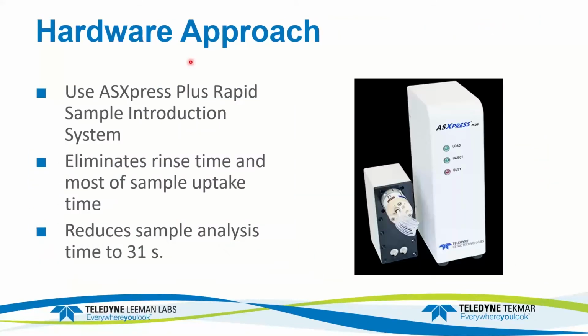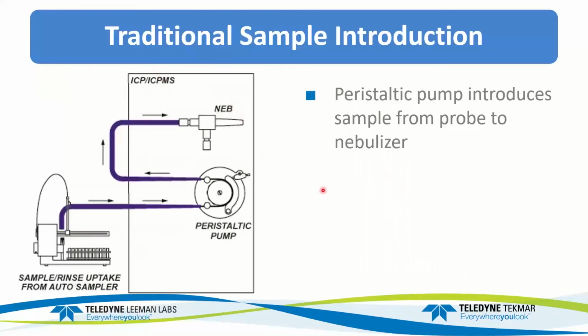All right. Then the second approach was a hardware approach. And this is using the ASXpress Plus Rapid Sample Introduction System. This is a valve system that can basically eliminate the rinse and most of the sample uptake time by switching the valve. And we'll go through how that works. By adding this, we were able to reduce the analysis time to just over 30 seconds. So 31 seconds of analysis time for the two replicates. Okay. So how does the valve system work?